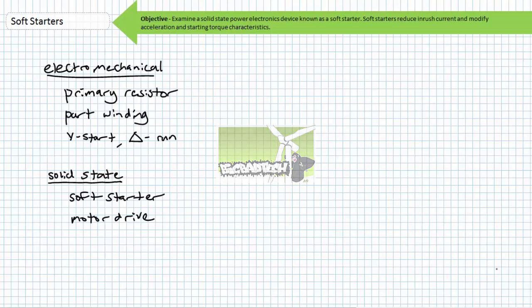do so now. As you are no doubt sick of me reminding you, the direct and instantaneous application of full voltage to a motor at standstill produces a tremendous surge of current known as inrush. Although brief, inrush current can place an unnecessarily high demand on the electrical distribution network, and industries often pay a financial penalty for such events. Additionally, the abrupt acceleration of a motor from standstill may damage the mechanical linkages like belts, chains, shafts, gears, and couplings the system uses to manipulate the applied load.